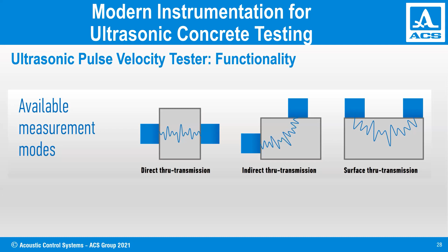So this is how it is implemented in our A1410. Just choose the transmission type, direct or indirect, and then the instrument. We choose the base value. For example, in this case, it's 150 millimeters. This is the distance between the transmitter and receiver, and we obtain the sound velocity value in meters per second. Or if the instrument is calibrated, we obtain the value in megapascal directly, the compressive strength value. So here I will show a short movie. Oops. I have removed the movie. It's okay.